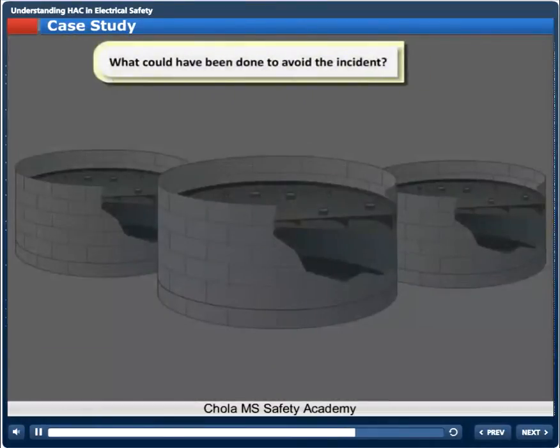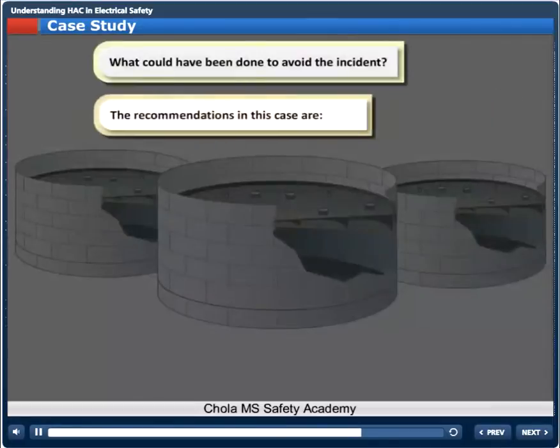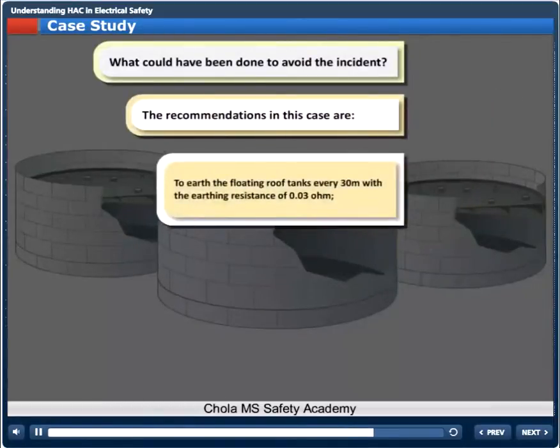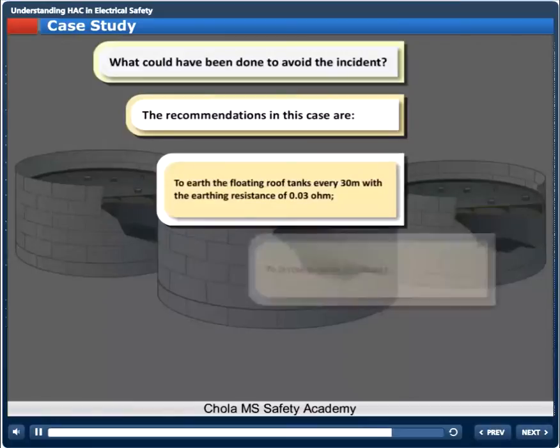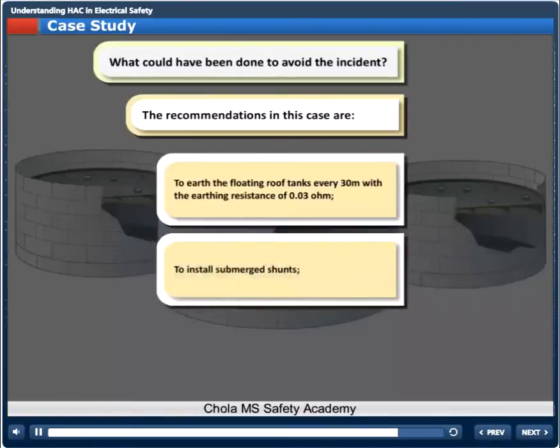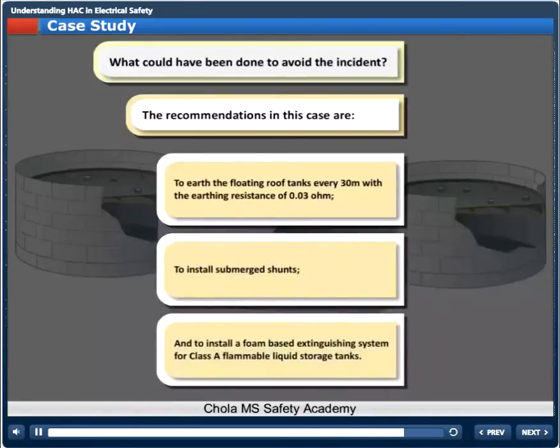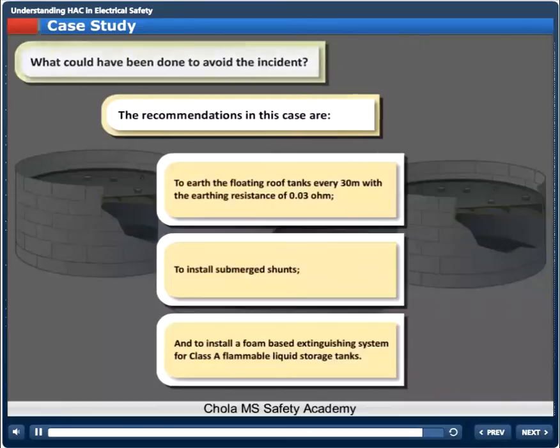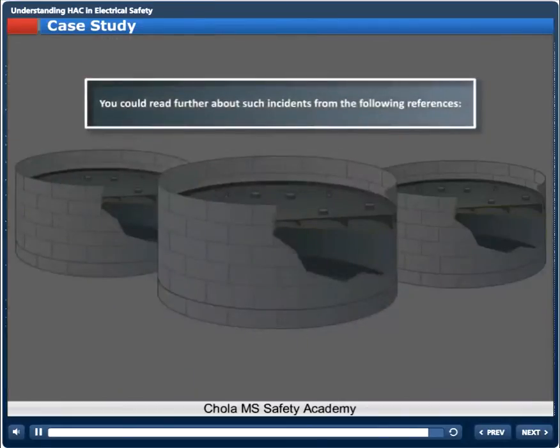What could have been done to avoid the incident? The recommendations in this case are: to earth the floating roof tanks every 30 meters with the earthing resistance of 0.03 ohm, to install submerged shunts, and to install a foam-based extinguishing system for Class A flammable liquid storage tanks. You could read further about such incidents from the following references.